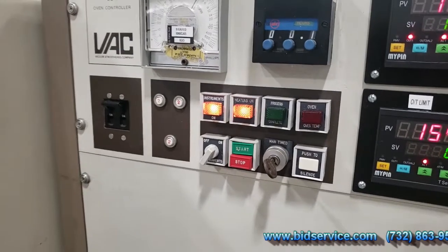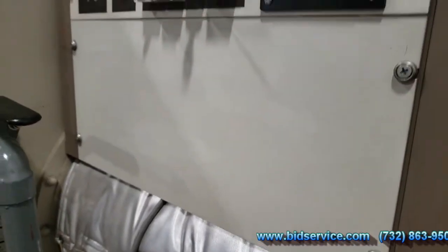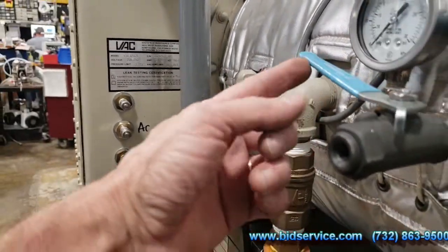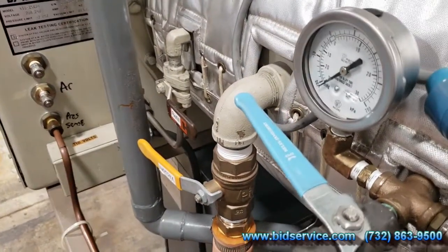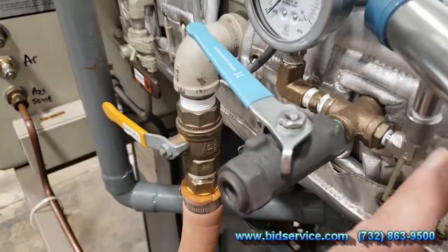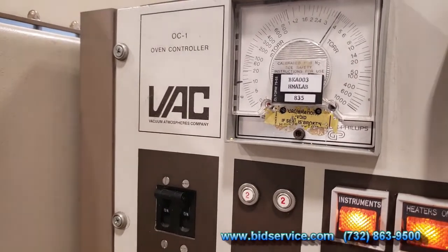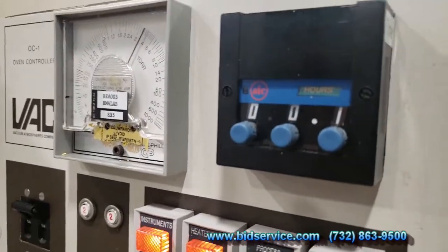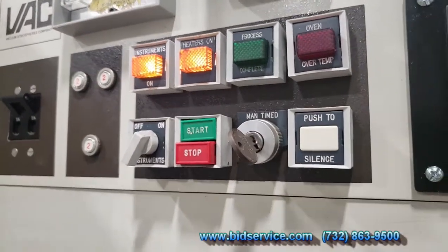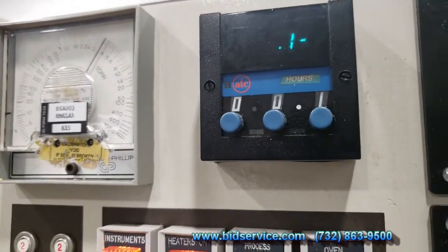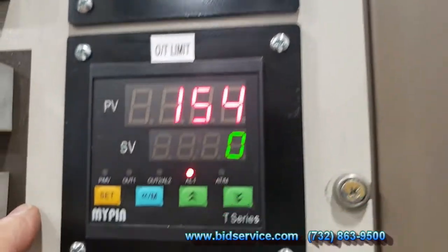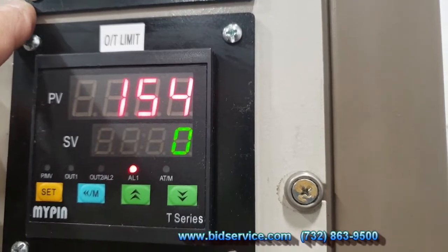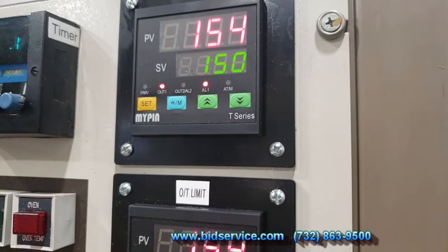Again, we're controlling at 150 degrees on this chamber. It works identical to the other one. Vacuum inline, refill. You want to vent the atmosphere. You have the two gauges, one that reads down to 30 inches of mercury, and the other here is a convection gauge too. You have the timer here, all the standard controls. You want to switch over to manual time to see which one's on. And then you have your temperature controller and your over temperature limit set up the same way. I believe you can bring this up to 200. The temperature controller's maximum temperature is set at 200 Celsius.